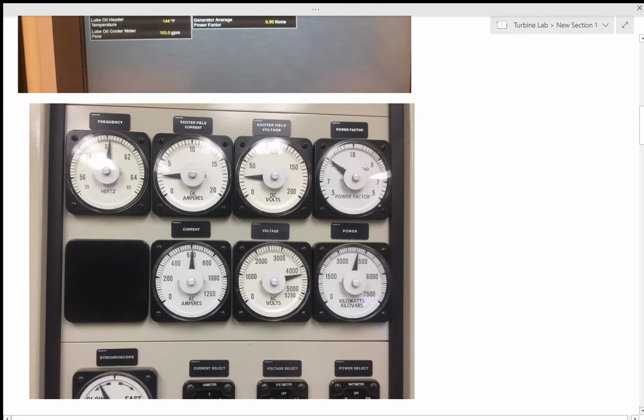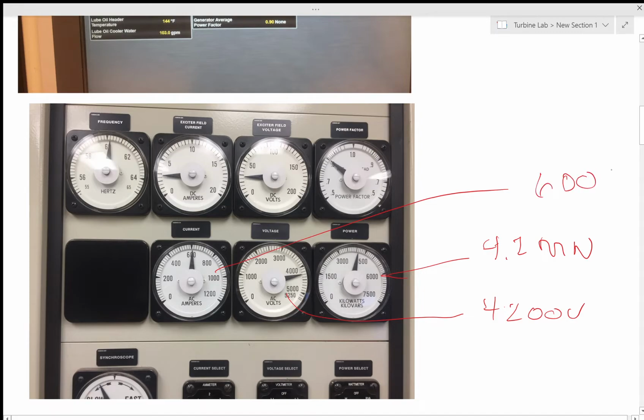Also on that panel, you'll see the operators over there can figure out exactly what's going on. Make sure that the generator is putting out exactly what we want. So you see it's putting out right about 4.2 megawatts when I took this picture, and the voltage is hovering around 4,200 volts, and we're putting out just a little over 600 amps on this thing at this time. And we have two circuits. We have 4 circuits on the main part of campus, and then 2 circuits that'll take this excess power down to Tortuga substation. You get a little more into it, you'll see that our frequency is pretty doggone close to 60 hertz, which is what it's supposed to be. And that the power factor is 0.9 lagging.